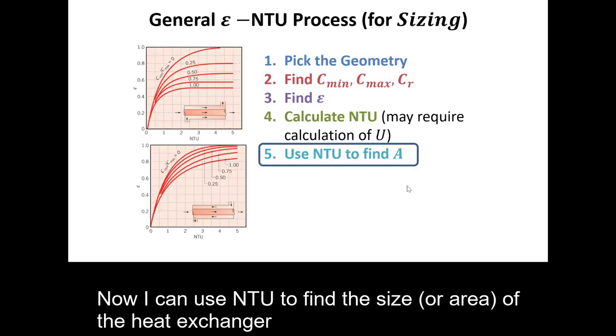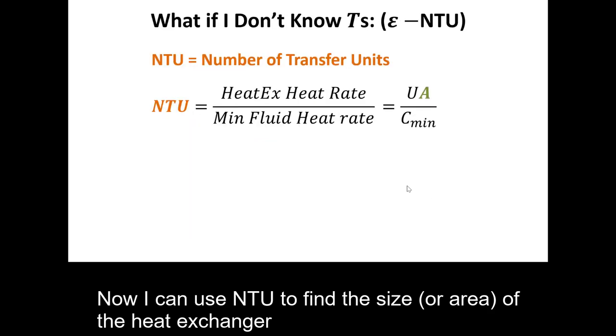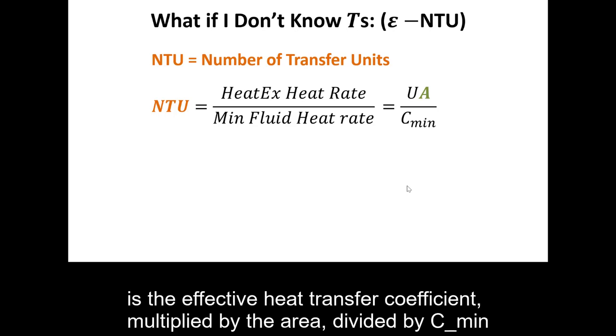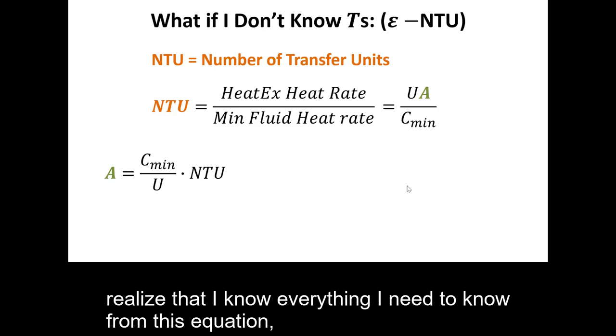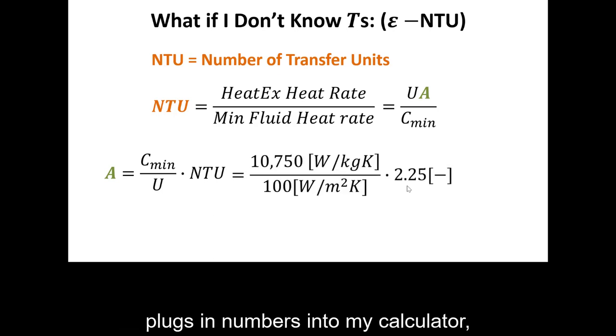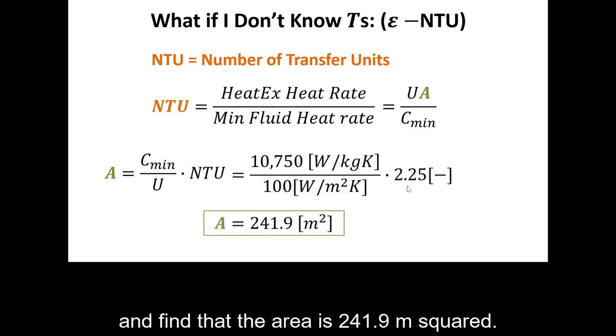Now, I can use NTU to find the size or area of the heat exchanger. The definition of NTU is the effective heat transfer coefficient multiplied by the area divided by C min. I can rearrange for the area, realize that I know everything I need to know from this equation, plug some numbers into my calculator, and find that the area is 241.9 meters squared.